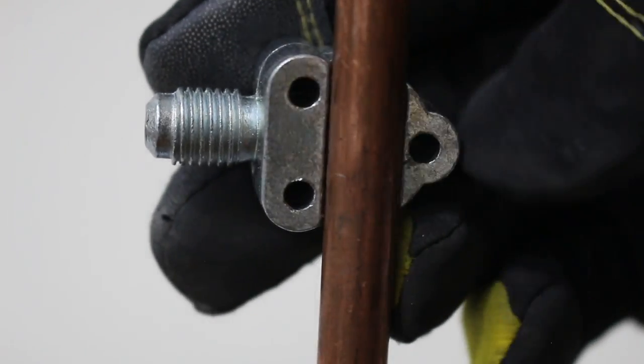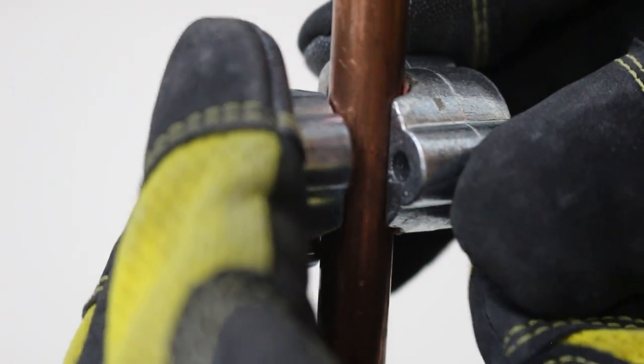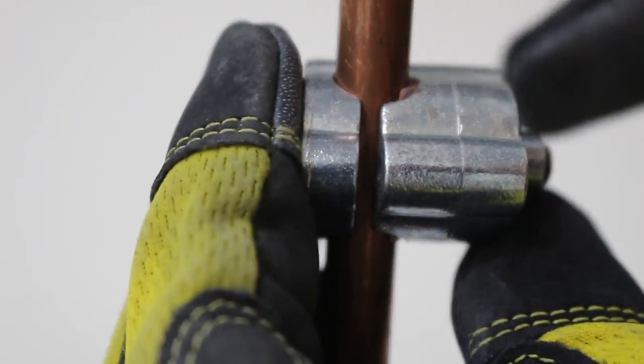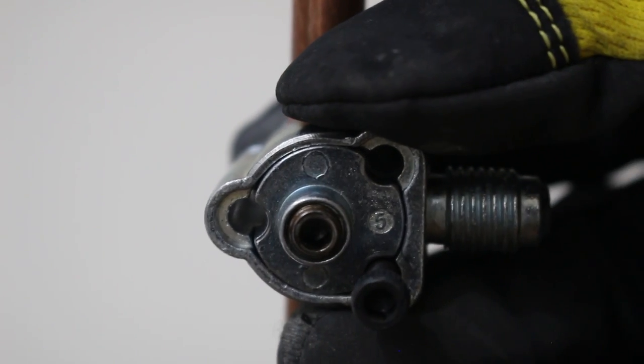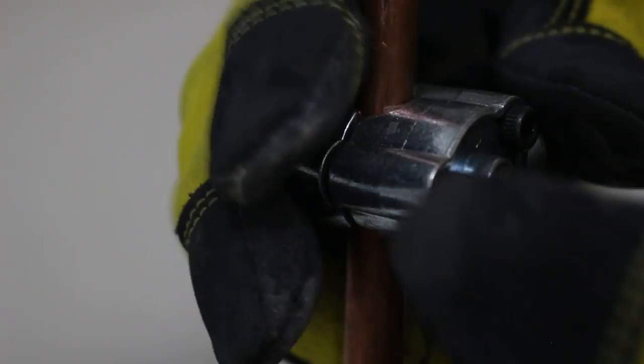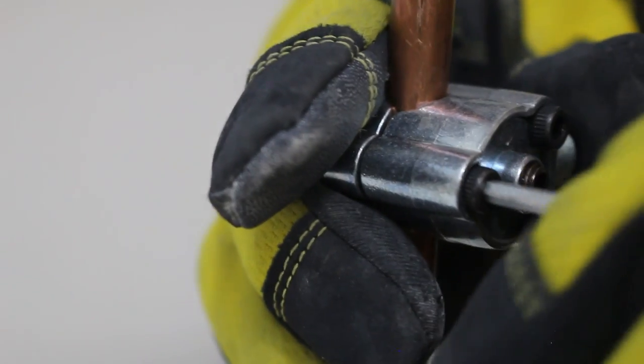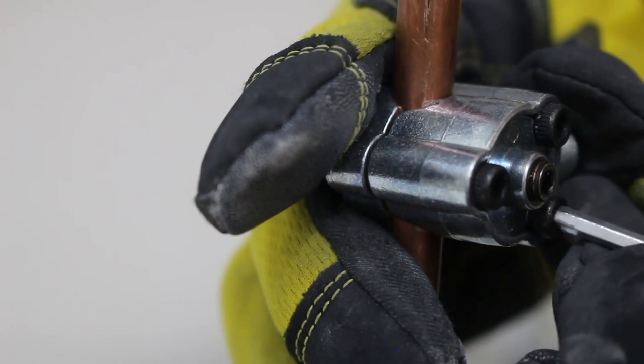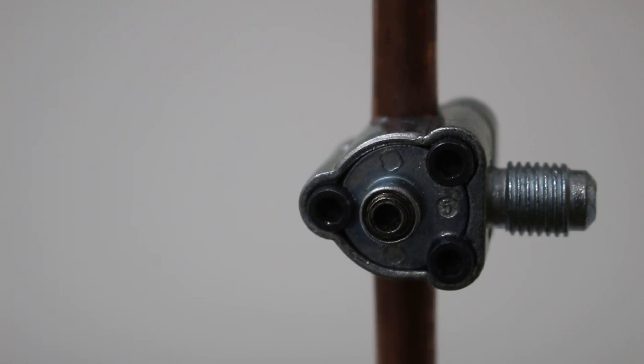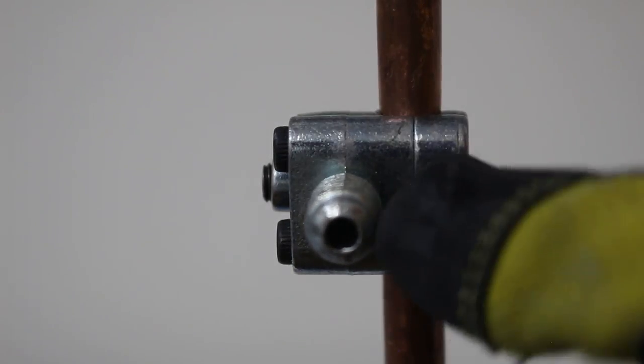All right, so in front of us, we have a 3/8th pipe. So, I will not be using the filler. And I will be using the smaller valve. So, now I can put one end here. See if it fits nicely. And then we can put the other piece. And from there, we put our 3 screws back and lock it down. The 3 screws we're putting back are the ones that we took off to separate the valve. So, right there, and tighten them all down. All right, so we have tightened down each of these 3 bolts. And across the seam, you can see we are perfectly snug.